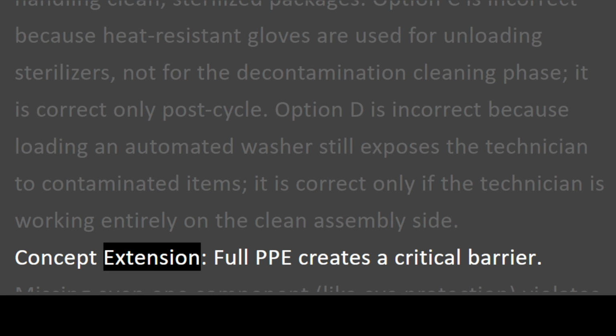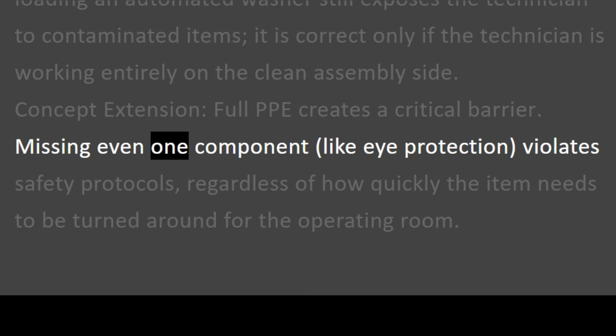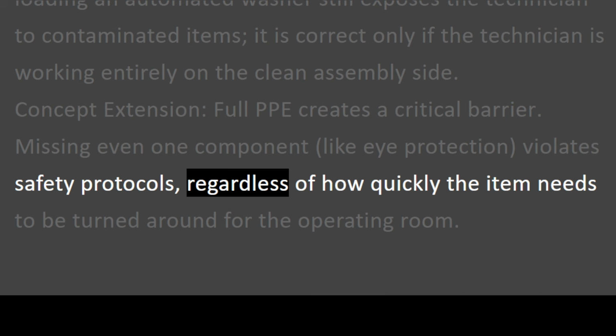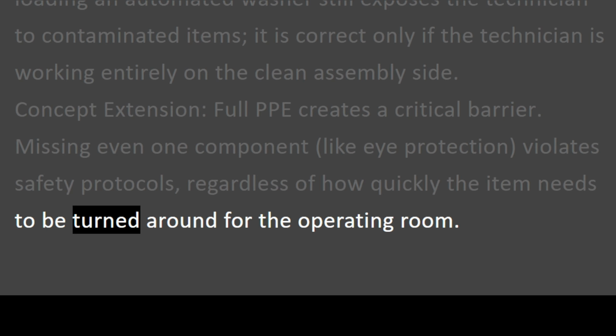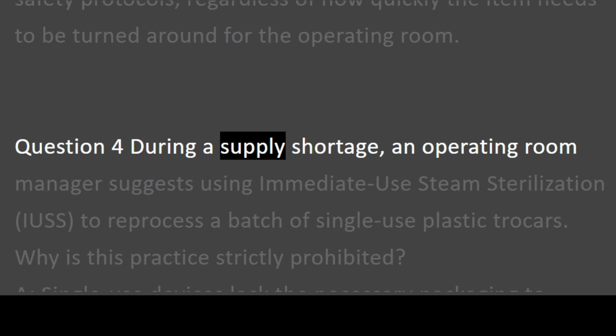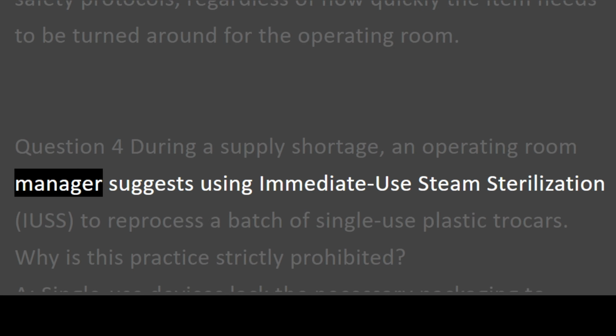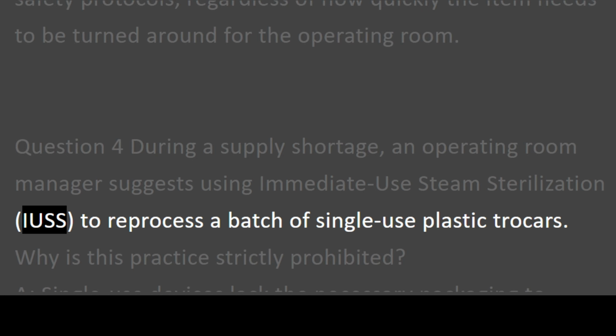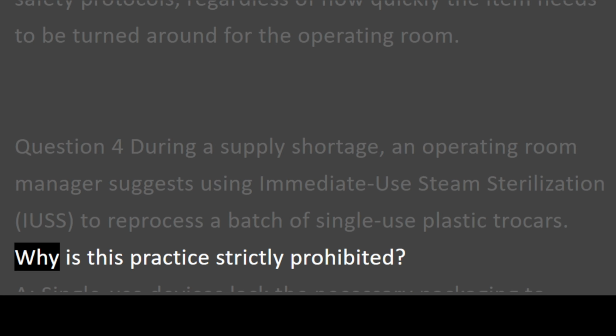Concept extension. Full PPE creates a critical barrier. Missing even one component, like eye protection, violates safety protocols, regardless of how quickly the item needs to be turned around for the operating room. Question 4. During a supply shortage, an operating room manager suggests using immediate use steam sterilization, IUSS, to reprocess a batch of single-use plastic trocars. Why is this practice strictly prohibited?